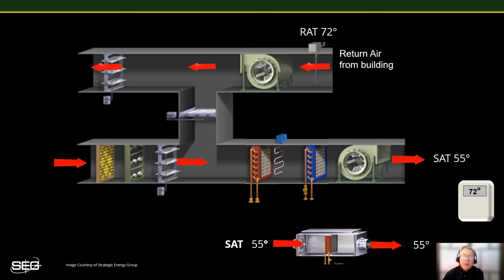Now, let's take a look at another example of simultaneous heating and cooling in air handler systems, where it's not a controls issue, but an equipment issue. This type of problem is hard to spot and often persists unnoticed for years. And again, we have an air handler, but with some slightly different temperatures and parameters. But note that the return air temperature is still 72 degrees, but the outside air temperature has risen to 68 degrees. Notice the outside air dampers are at 100% open now, providing free cooling via the economizer and resulting in a 68-degree mixed air temperature.